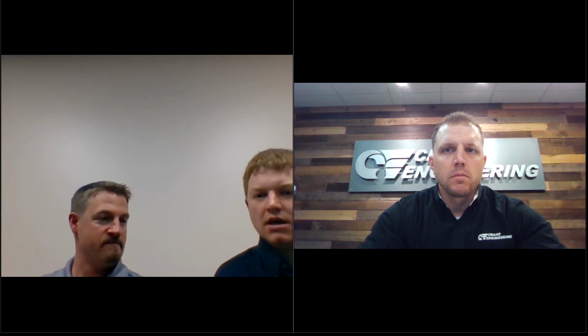I guess my take would be purge it once and see if you're getting buildup, right? If you've got a drain from the bottom, I would think it would be better to do a good purge and see what you've got. If we're talking about a water quench on the atmospheric side going to the drain just to wipe away buildup and things, that can just be a slight drip all the time.